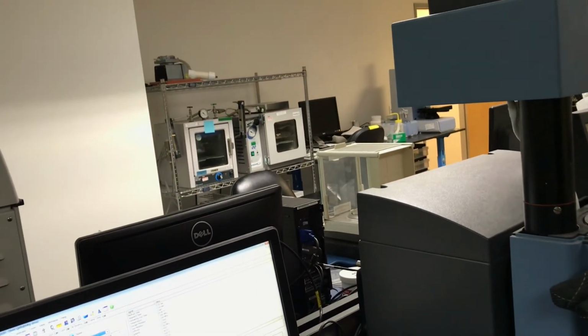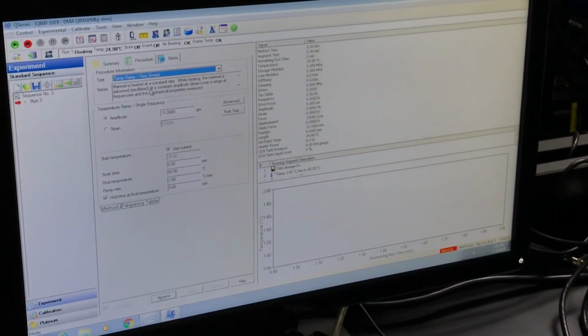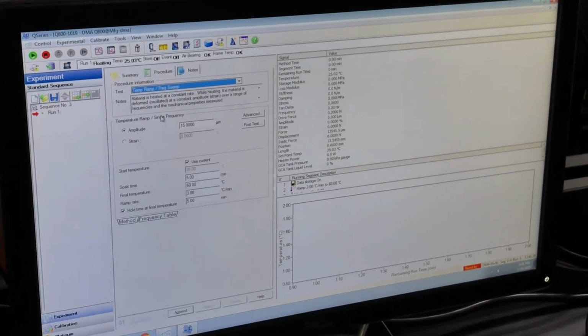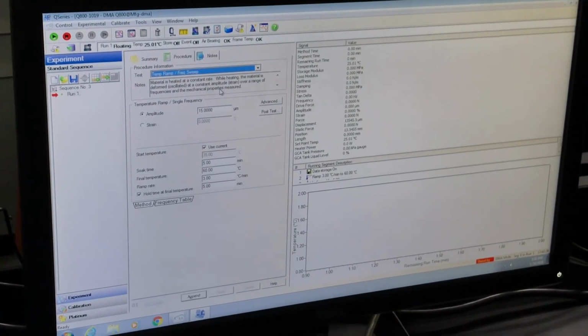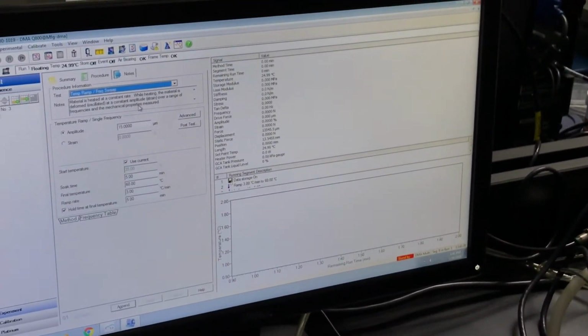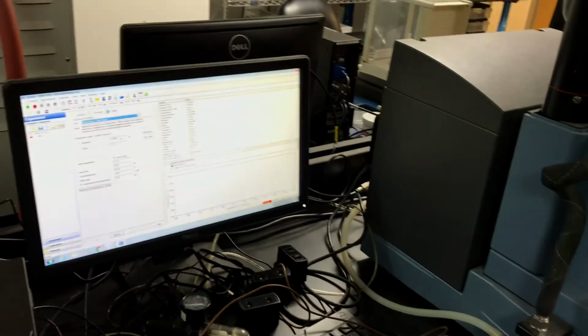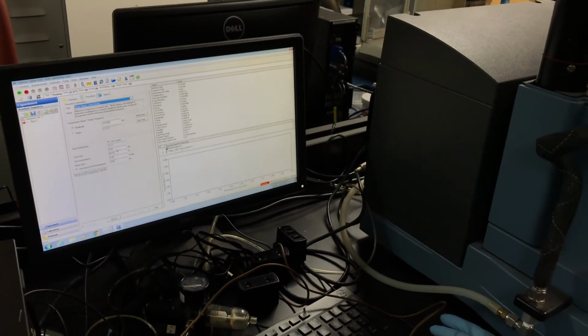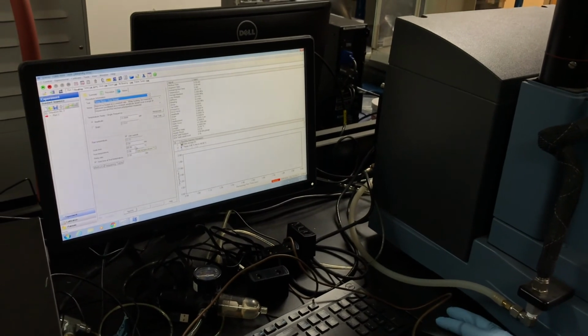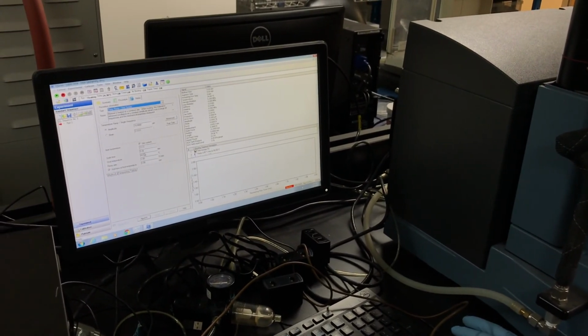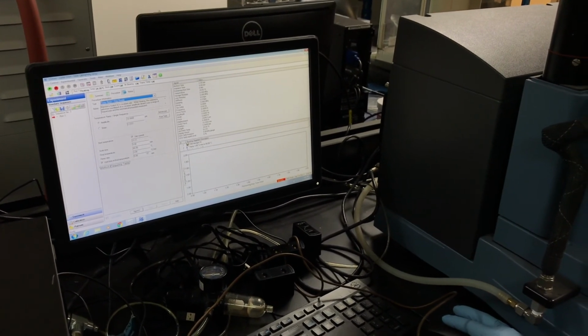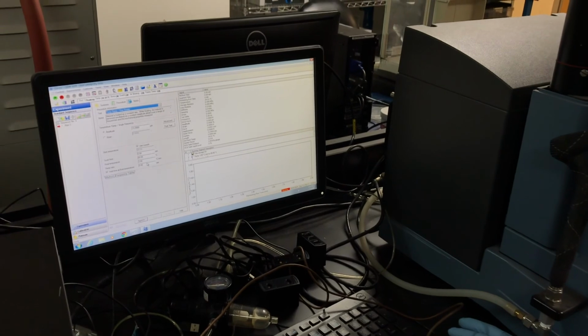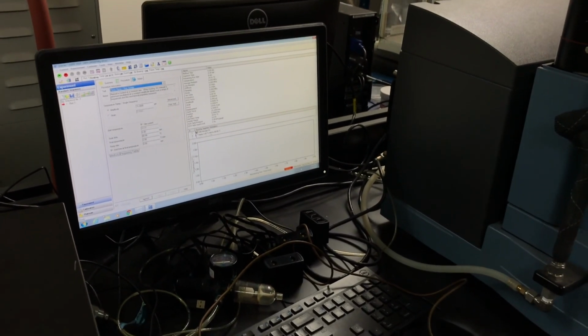But for instance, for this, if you want to go ahead and specify the procedure, a temperature ramp, the notes say the material is heated at a constant rate while heating, the material is deformed at constant amplitude over a range of frequencies. So you can change all that. And as it's oscillating up and down while heating, you can track the mechanical properties of that material. So there's a lot of different things you can do. In terms of the procedure, you can change the temperature, the final temperature. Let's say you start at 35 C and you want to ramp up to 60 C at a rate of 3 degrees C per minute. And then you can hold at that final temperature for some amount of time.